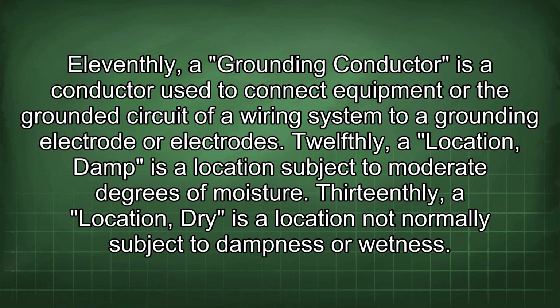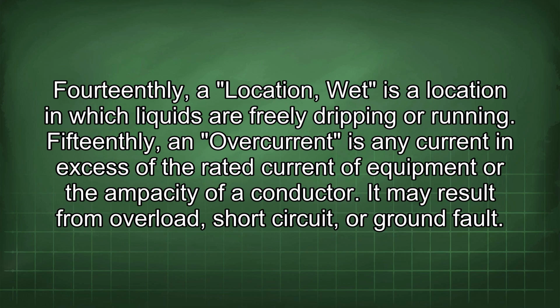Twelfthly, a location, damp, is a location subject to moderate degrees of moisture. Thirteenthly, a location, dry, is a location not normally subject to dampness or wetness. Fourteenthly, a location, wet, is a location in which liquids are freely dripping or running. Fifteenthly, an overcurrent is any current in excess of the rated current of equipment or the ampacity of a conductor.